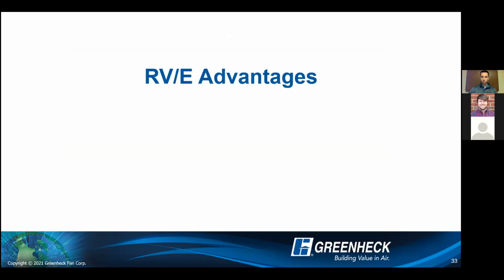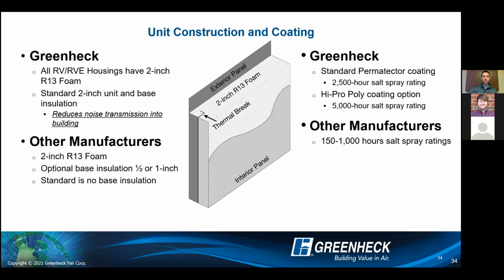So I want to end here with some RVE advantages, just where we're at in the market in relative terms to what we offer on our equipment. And first one's obviously construction and coating, and some of this might be repeats for you guys, but hopefully you're starting to see that in the field if you're utilizing our equipment. But with our RVE housings, it's double wall construction, and we have 2-inch R13 injected foam. And I want to make the injected part clear, because a lot of the times that we're seeing other competitors utilize 2-inch R13 foams, they're using panel boards, which means there's a lot of gaps and not enough thermal breaks in that type of panel or in that type of foam construction.